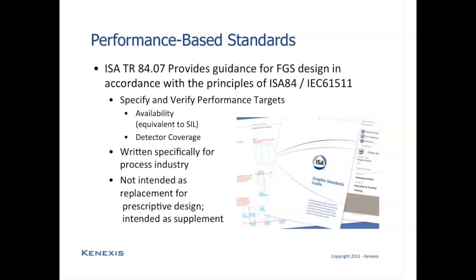And the other thing to note is that this technical report is not intended to be a replacement for the prescriptive design. The prescriptive design techniques are still going to apply to a lot of areas of a facility. So if you were looking at a typical refinery, you would still want to design the fire and gas systems in the control rooms, in motor control centers and other occupied buildings using the requirements in NFPA 72. It is not a replacement. It is only a supplement for things like toxic gas detection and fire and gas detection in outdoor areas.